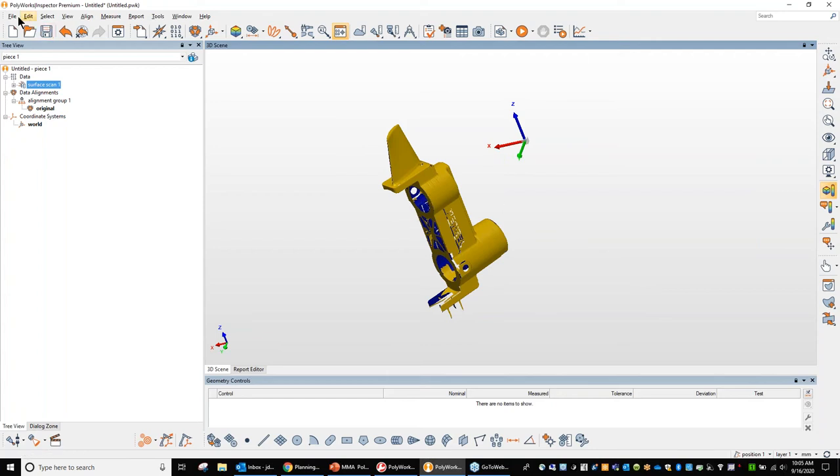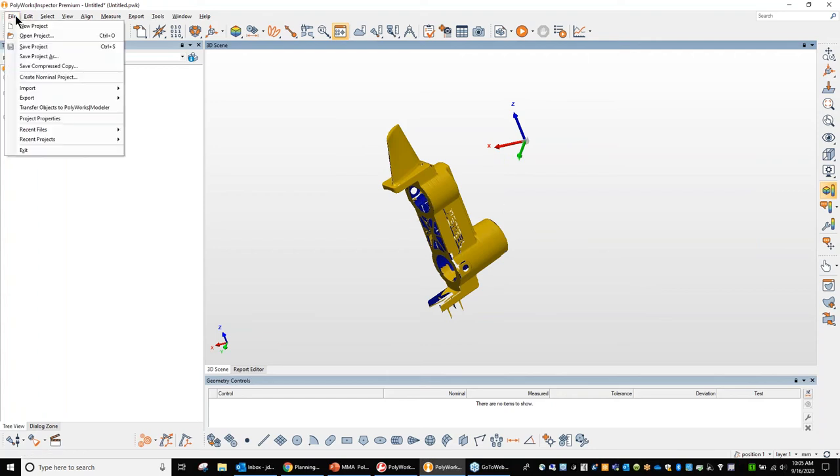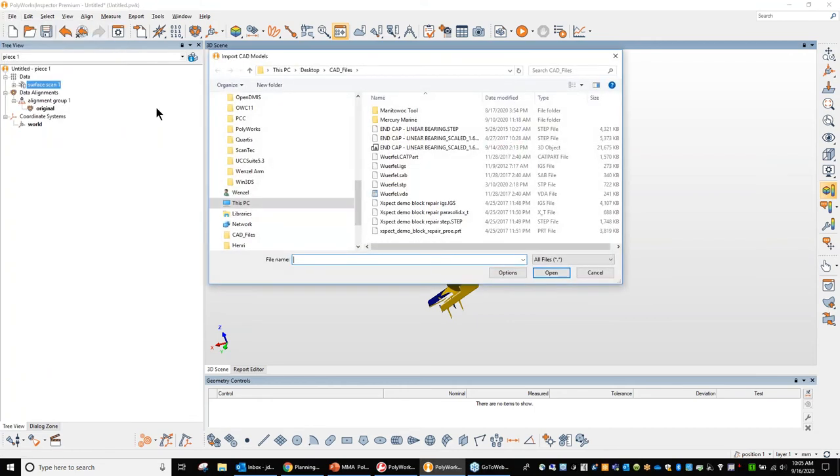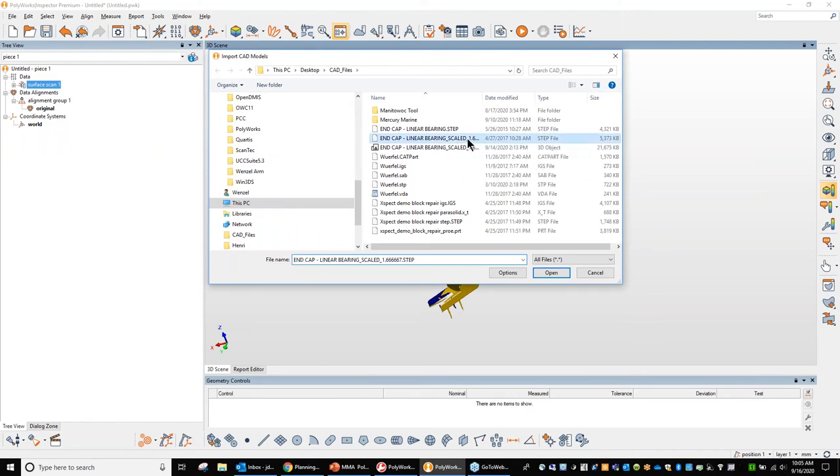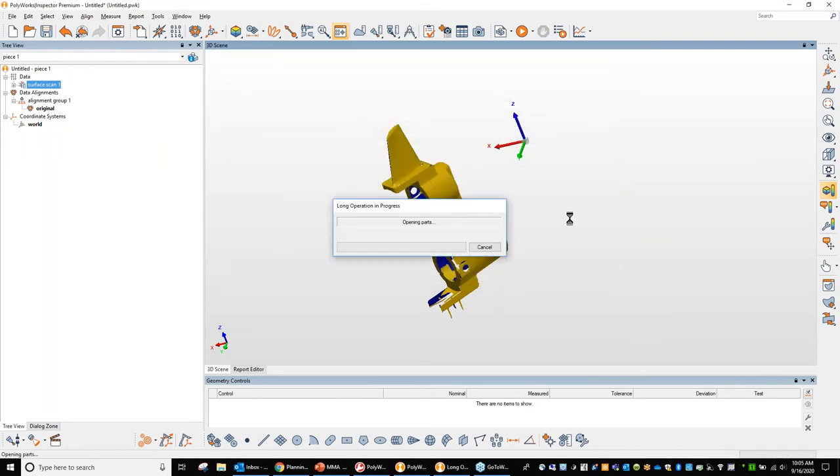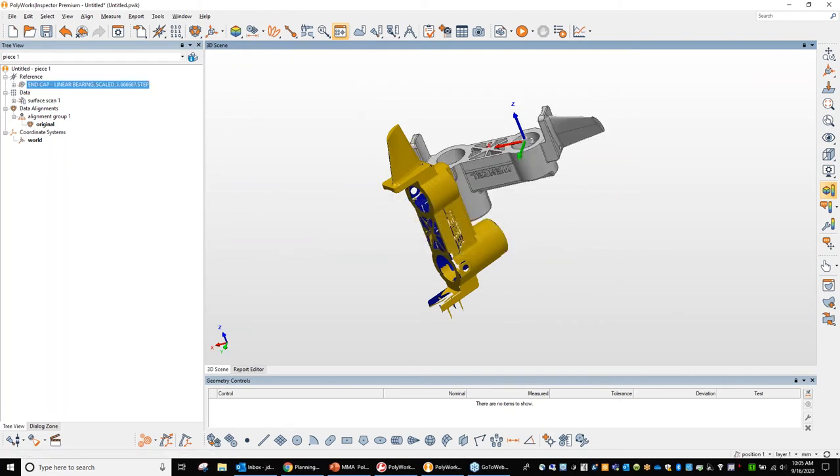So to do that, if I go here to file and I go to import and I look at importing the CAD models. Here I can go find that CAD model and select it and open that model and let it import into the system. And you'll see that the scan data of course, isn't lined up to the CAD model. The CAD model comes in at the base of the arm. That's the coordinate system. And the CAD model is just wherever it's at in that volume of the measuring arm's volume.